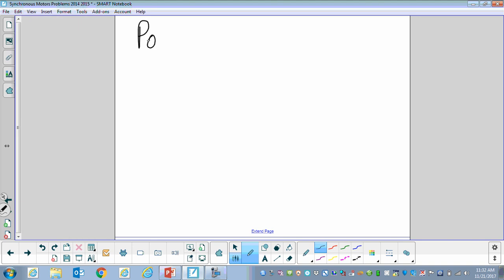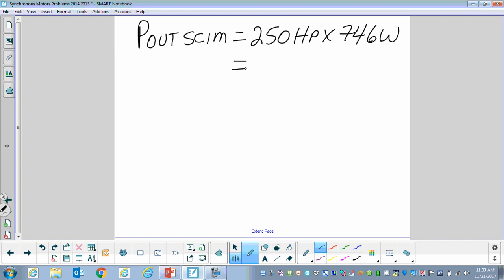We're going to start with power out and calculate that accordingly. Power output of the squirrel cage induction motor equals 250 horsepower times 746, which yields 186.5 kilowatts. We're dealing in kilowatts since we're working with numbers over 1,000 watts, VA, or VARs, so there's going to be some rounding involved as we go through the problem.